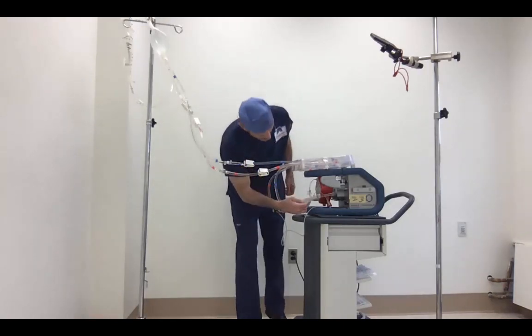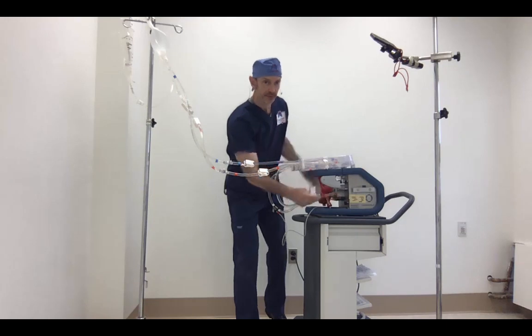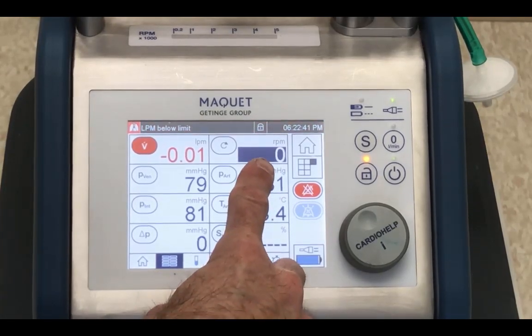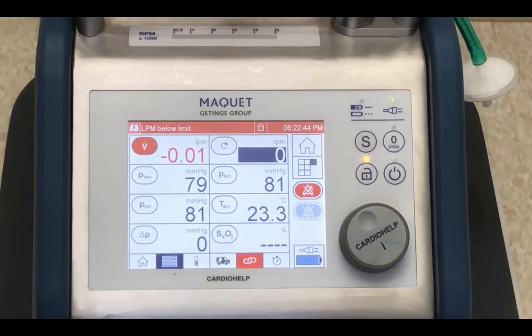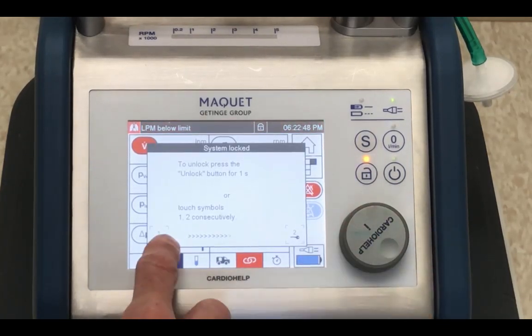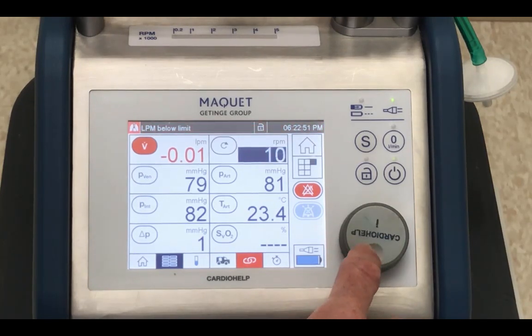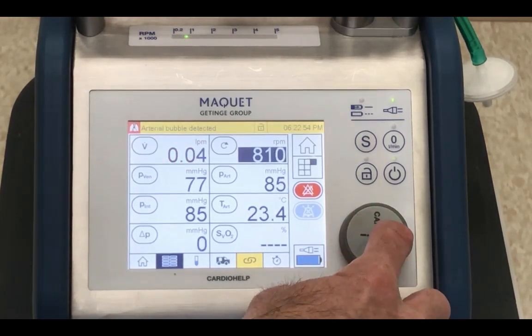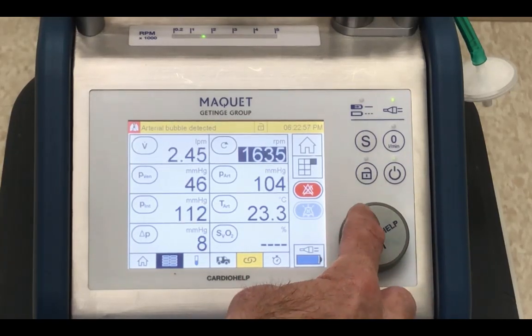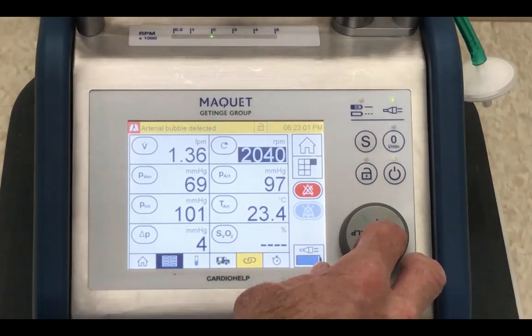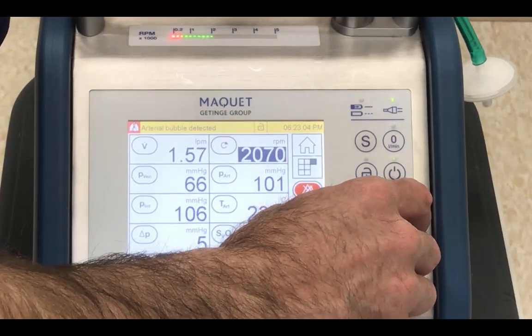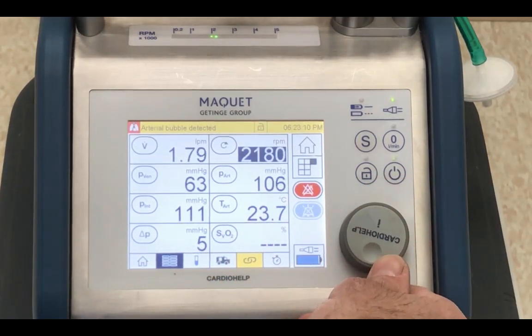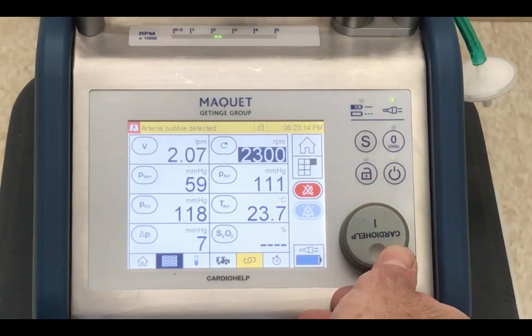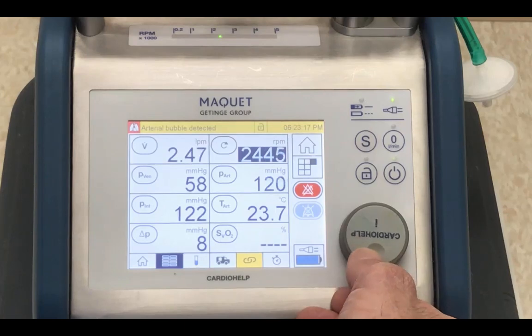So now that we have fluid down here to the pump, the next thing to do is to add some RPMs over here. So let's go ahead and turn up the RPMs. Manufacturer's recommendation is something like 3,000 RPMs for 4 minutes, and then 4,000 RPMs for 1 minute. See the fluid starting to move, the bubble's starting to move. And you can hear a sound. I can put my mic down there. You hear air breaking up and moving through the system.